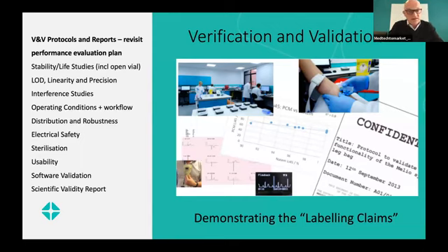And things like stability studies. So if your design inputs say it needs to have a shelf life of 12 months at room temperature, you make sure you have that data to support that. And normally you support it for 13 or 14 months, and then you have 2 consecutive time points that show stability, and then that way you can use the first one of those as your cutoff.